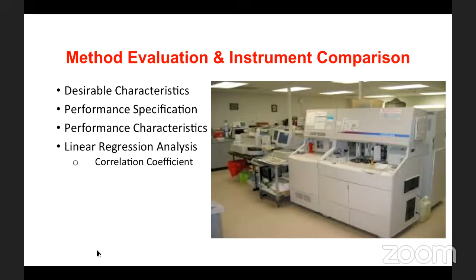Suppose you have one machine. You're happy with that machine. You're testing hemoglobin of different ranges in this machine, from 5 to 25: 5, 10, 15, 20, 25. What is your expectation with the new machine? Your expectation with the new machine is, I shall get a similar result.